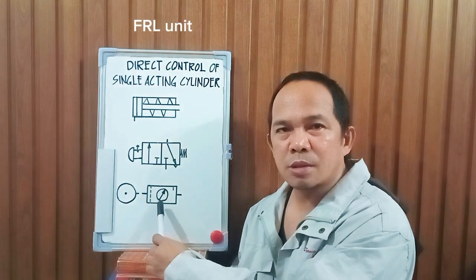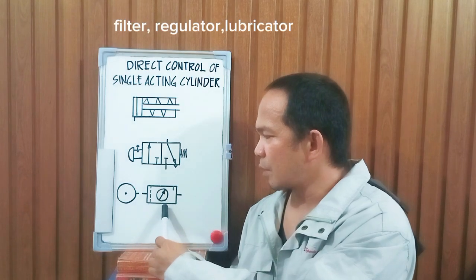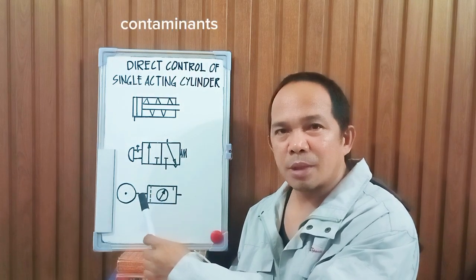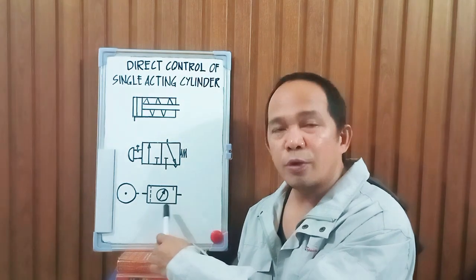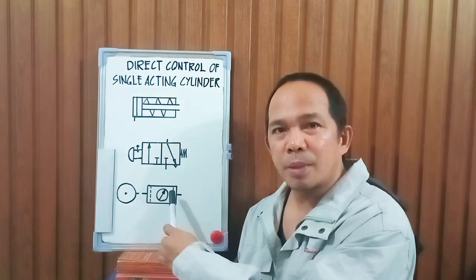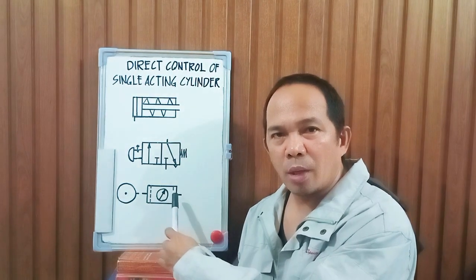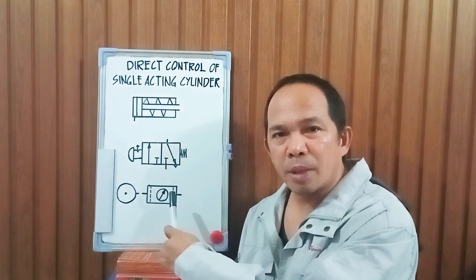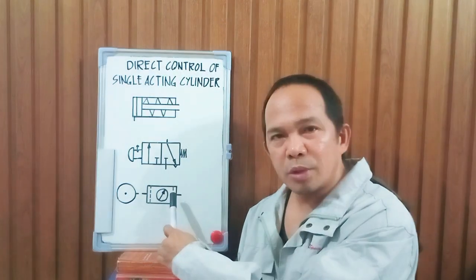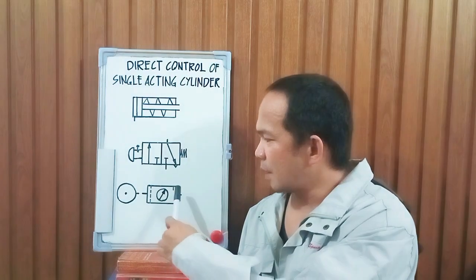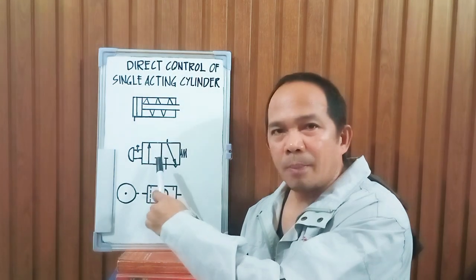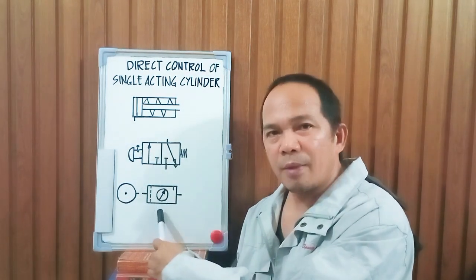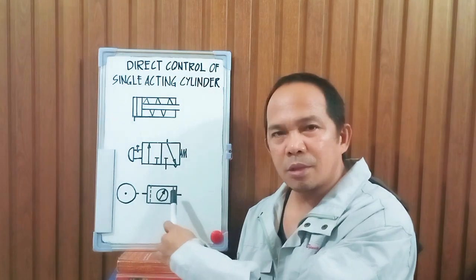Then we have here the FRL unit. What is this FRL unit? This is filter, regulator, and lubricator. Why do we need a filter? Because there are contaminants in the air like dust and other contaminants, so we have to filter the air. The regulator is for the pressure — for us to monitor the pressure. And the lubricator: why? Because these cylinders and valves are made up of metals. If we inject air with no lubricants, they will seize up after some time. So we need to put a lubricant — a very small amount of lubricant enters these metal parts to avoid the seizing up of these devices. So this is your FRL unit — stands for filter, regulator, and lubricator.